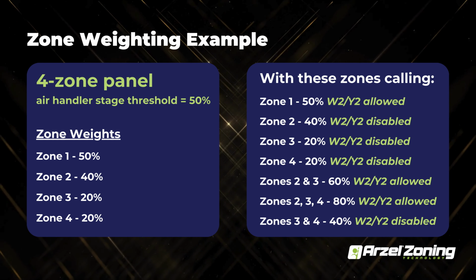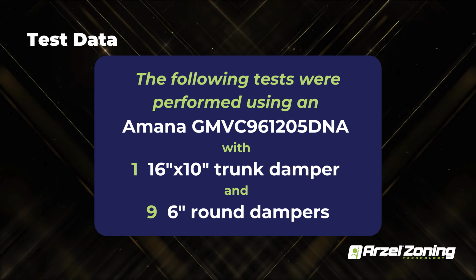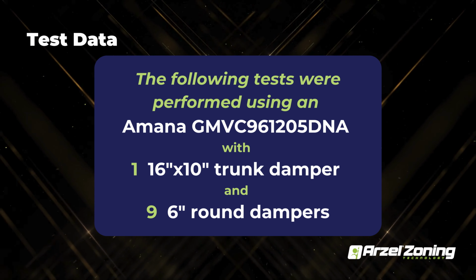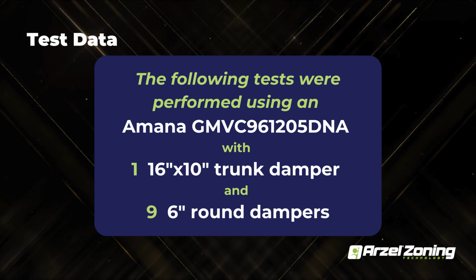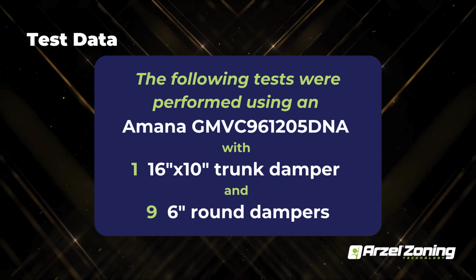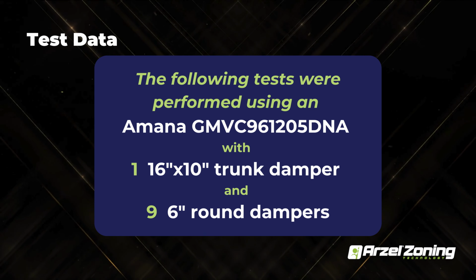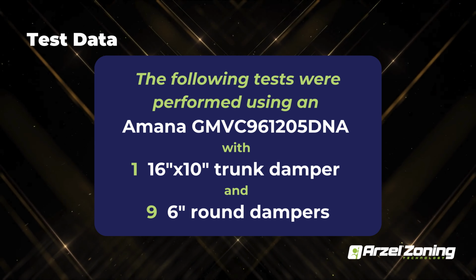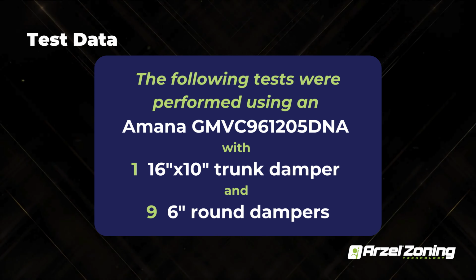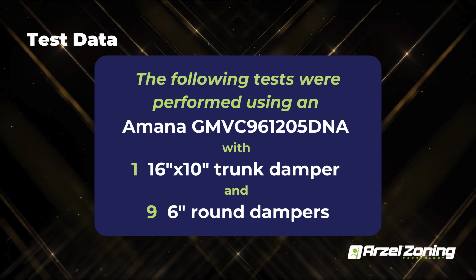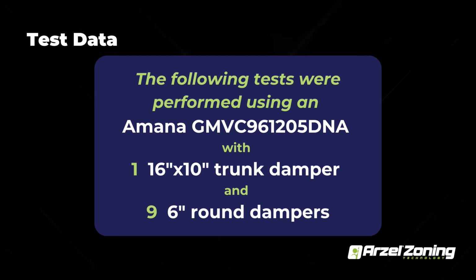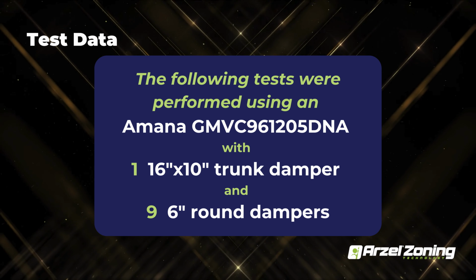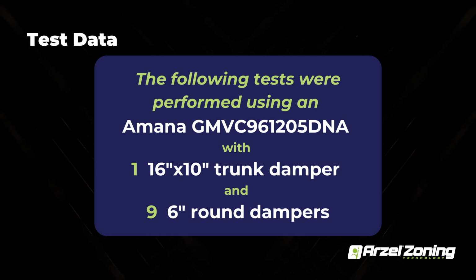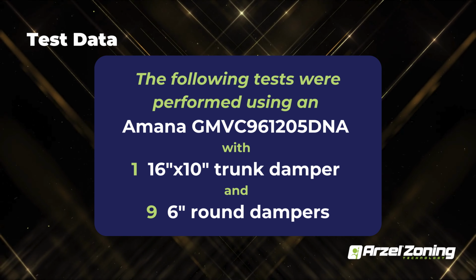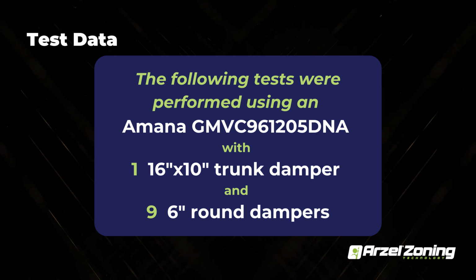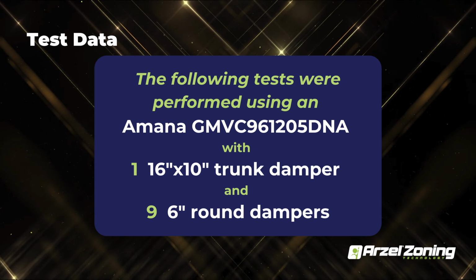So the next thing that we did here, this is a test station that we have set up in our lab. It's a 5-ton system with a Amana GMVC96, so it's a variable speed 2-stage furnace that we have back there. This is not wired up to be communicating. It gives you the option of that, but the communicating feature is taken out. So this is just first and second stage outputs, relying on a Y1, Y2 output or a W1, W2 output. And on this system, we have one 16 by 10 trunk damper and 9 6-inch rounds. This is going to be a 5-ton system, so it gives us our 2000 CFM of ductwork.